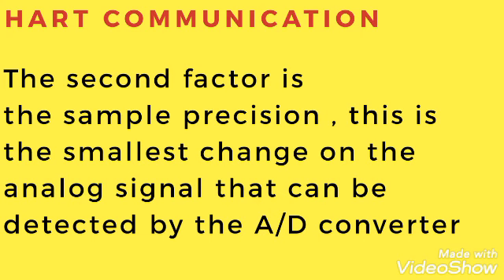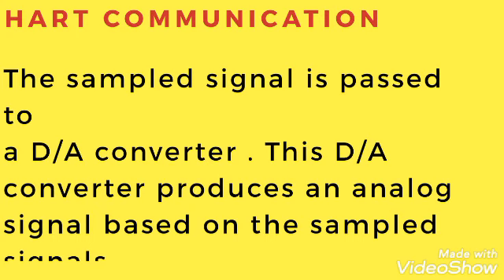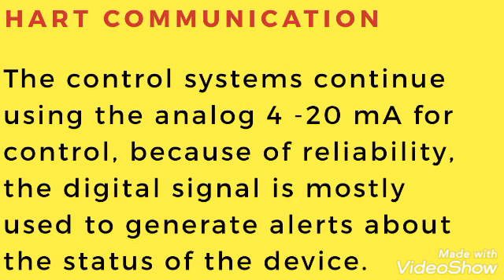The digital signal is passed to a signal processor to get a more accurate value. The signal processor also generates the HART digital signal that overlies the analog output. The sampled signal is then passed to a digital-to-analog converter, which produces an analog signal based on the sampled data. The control system continues using the analog 4-20mA for control because of its reliability.